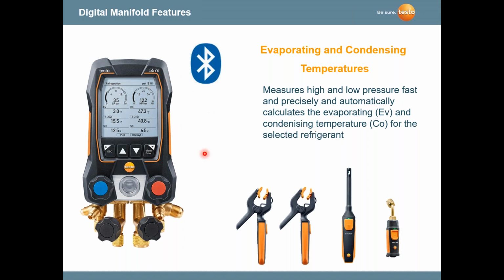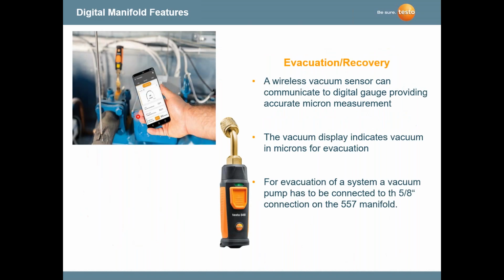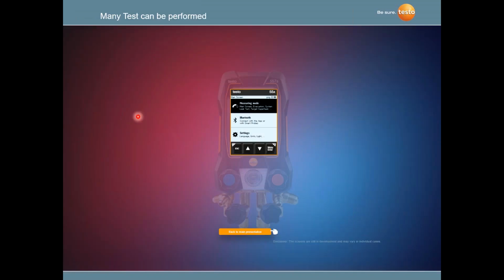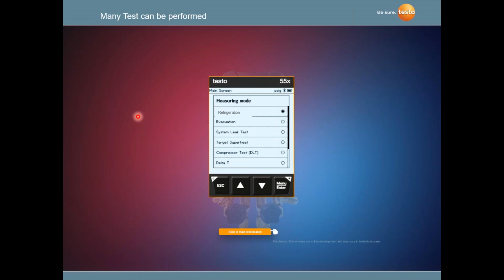Today's instruments have the capability of uploading 4 smart probes, Testo smart probes, not only the temperature probes and the relative humidity probes, but we introduced a vacuum probe, which ties into this instrument. So you no longer have a vacuum sensor that's internal in the instrument, which we found out to be inaccurate because of the leaks that were created in the hoses and the connections when you do a deep vacuum. So now the whole vacuum side of these gauges is a separate probe that shows the micron measurement on the digital gauge. And there it is, a close up of the gauge itself.